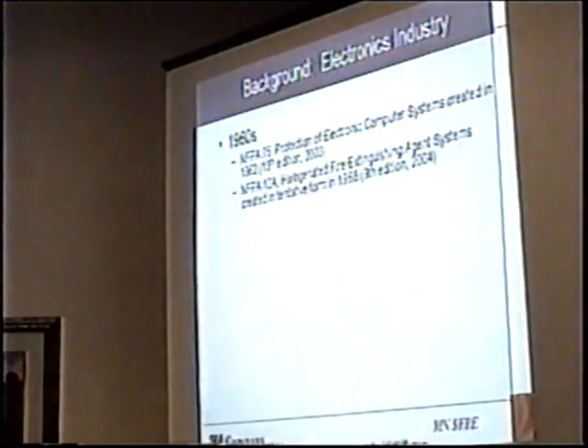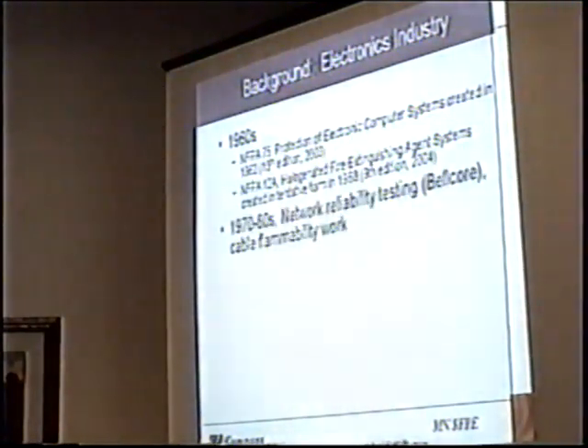You look at NFPA 75, this is back in the 1960s now. NFPA 75, which now is 13th edition as of 2003. That's fire protection for electronic computer systems. Remember, they had the big UNIVAC 1108 computers that filled up this entire room. Different scenarios than we have today. NFPA 12A was developed in 1968 in tentative form, and in 1972, I think it was, that it finally became a standard for halogenated fire extinguishing agent systems.